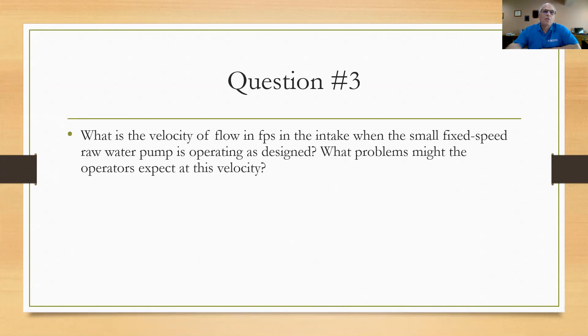Question number three states, what's the velocity of flow in feet per second in the intake when the small fixed speed pump is operated as designed? And once you've done that, why don't you list what problems might the operator expect at that velocity? Okay, so they're wanting you to figure out the velocity. So we got to get some information from the tables here. You see that the small pump is rated at 1,750 gallons per minute and they're asking us to use that flow rate as designed. So we're going to use 1,750 flow rate.